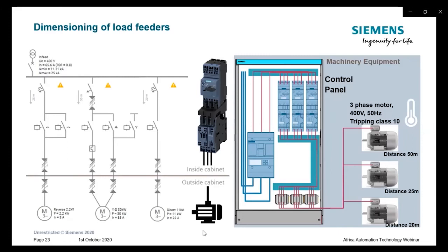And those are usually equipped inside of the control cabinet and are going to operate the loads during specific environmental conditions, which also rely on the temperature inside of the machinery. The temperature inside of the cabinet could be much different, and the loads themselves may also be operated at different distances from my control panel. Let's go into a calculation example of how intelligent software tools support your engineering for the load feeders.